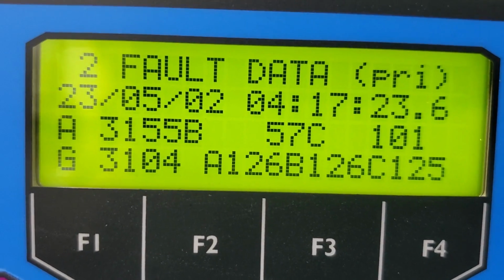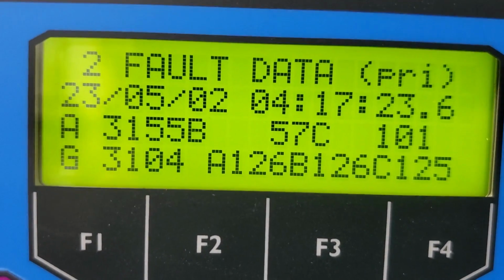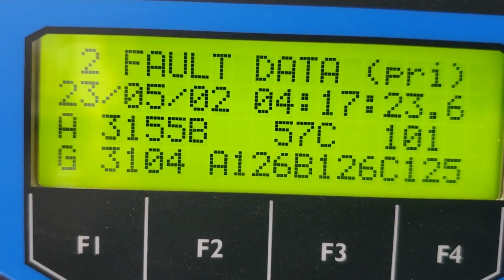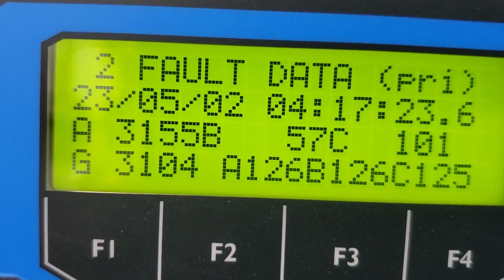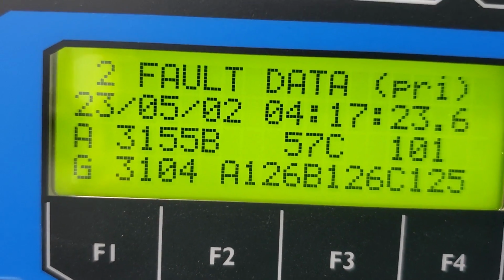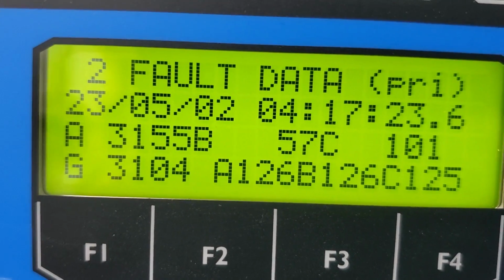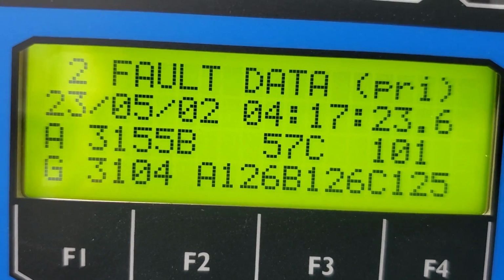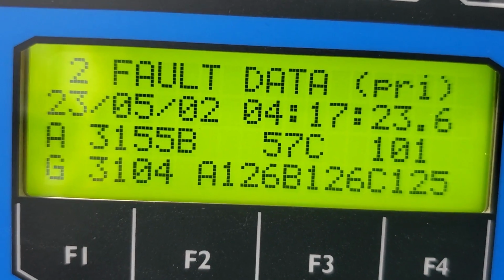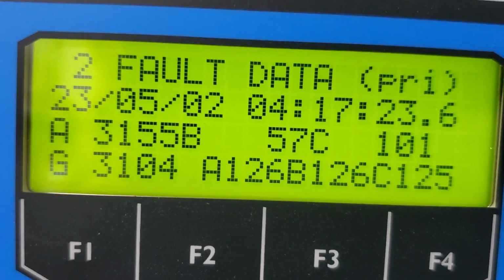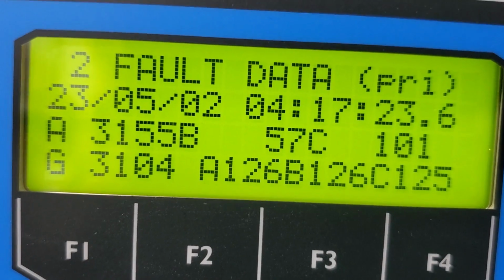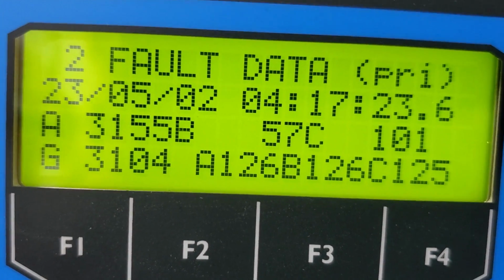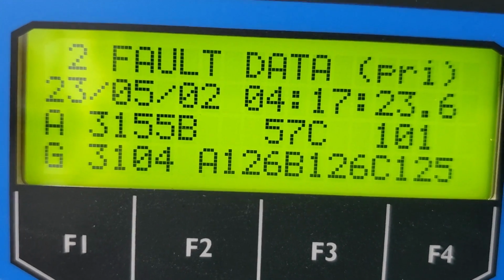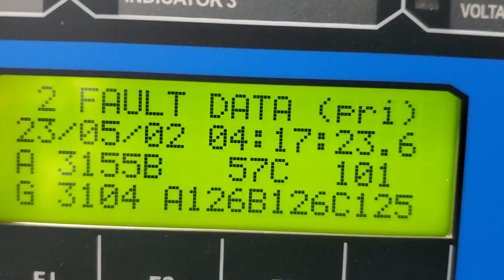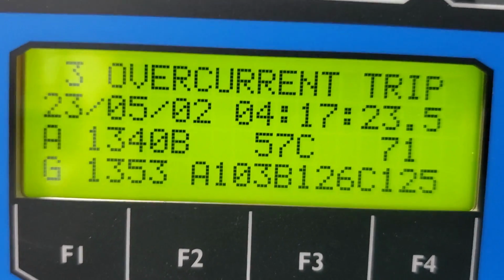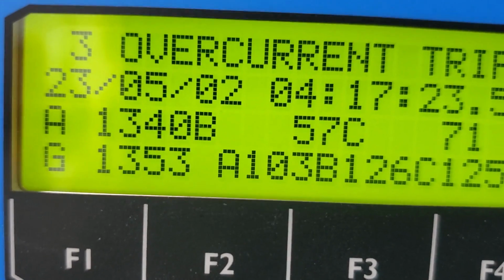Also, if the line is out when I come in here to lock out the recloser before I go and do the patrol, where I see a fault on A to ground, if it was, let's say, A phase and B phase, I can assume maybe a branch from up top fell and landed across 2 of the 3 phases. That's an extremely high current fault, so whatever made contact made really good contact. A tree during a rainstorm that's quite conductive could do that. It's probably fairly close to the substation, being such a high current fault as well. As we scroll through, here we have an overcurrent trip that's a little more common, 1340 amps.